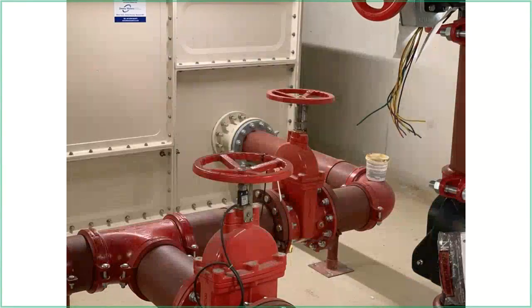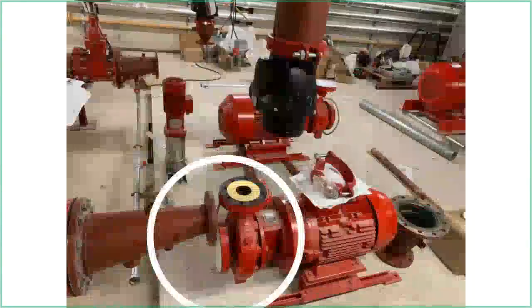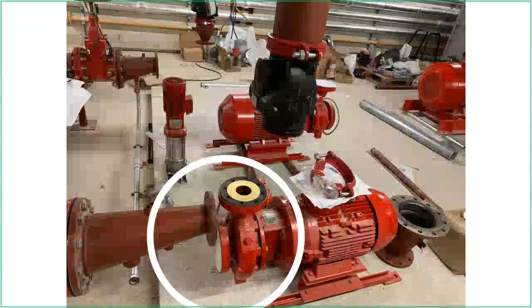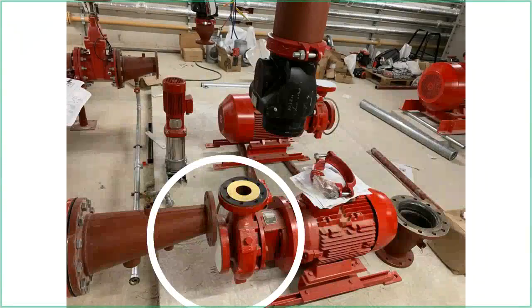That's a bit better. So that's all shiny and new, installed. You can see on the top right-hand corner all those wires coming out of the monitored valve. That hasn't been done yet, so that needed to be wired and monitored somewhere. This picture is showing, in the white circle there, the misalignment. On the left-hand side there will be the tank, and on the right-hand side we've got the fire pump, and there are two flange connections there, and they should line up. The problem in this instance was that the plinth wasn't built high enough, so that needs to be corrected. Ideally we want to find out as soon as possible so it can be fixed, rather than waiting until one week before final handover and finding we've got a problem with the fire pump.